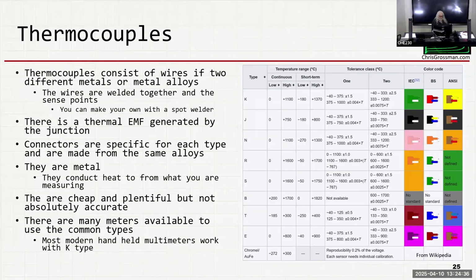The issue with thermocouples is they're metal, so if you connect them to something, they're going to conduct heat away or into whatever you're trying to measure. Sometimes I'll try to get the finest thermocouple wire I can if I'm measuring an electrical circuit with it. They're cheap and plentiful, and there's lots of instruments that will measure them. That's typically what you'll use in a test setup.